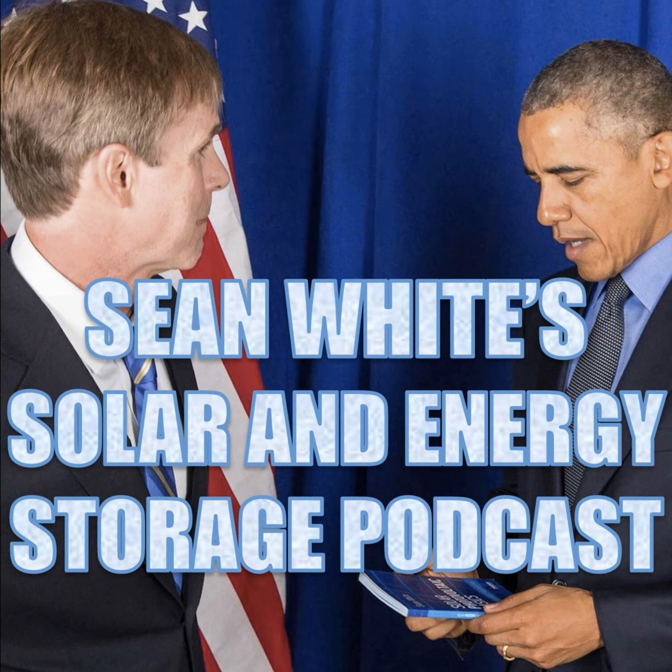The SolarABCs website, and I'm always going there for these temperatures, that's solarabcs.org. If you want, you could go /permitting to get you there quicker. It provides a readily accessible source for the ASHRAE data. You can search for your location based on zip code, and the site returns ASHRAE data from local weather stations. The data include 2 high temperature values, the 0.4% temperature value and the 2% average values in degrees C. Most people in the solar industry use the 2% high design ASHRAE tables as the standard for design temperatures.